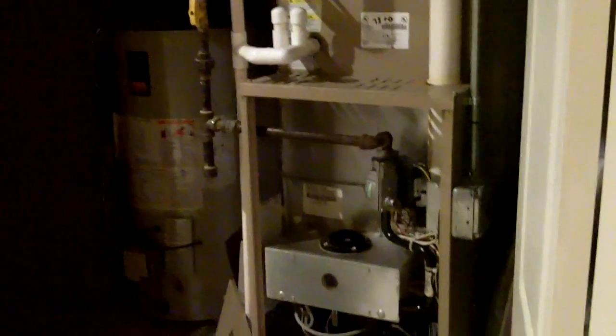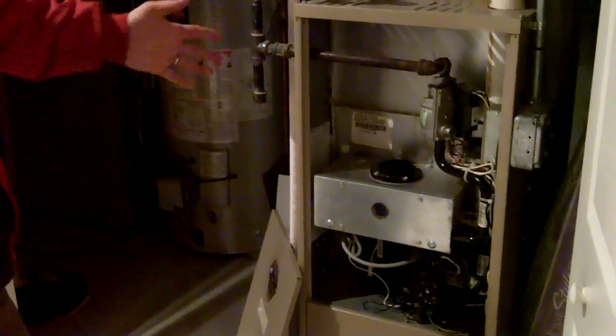So Joe, tell me what you're going to be doing here with the heater. We're going to check the heater to make sure everything's functioning properly, checking for any damage to the heat exchanger, which is the heart of the unit, to make sure we're not getting carbon monoxide coming back into the house. We're looking for leaks, rust, deterioration, things of that nature, and also explaining how the system works to you. So you actually take this apart and get into the meat of it? Open it up as much as I can—not going to tear it apart, but look and see as much as possible.